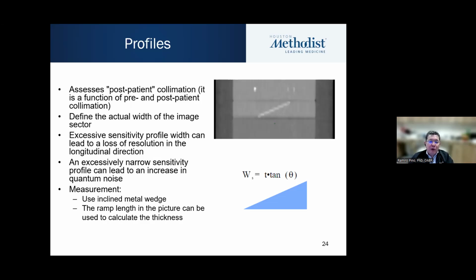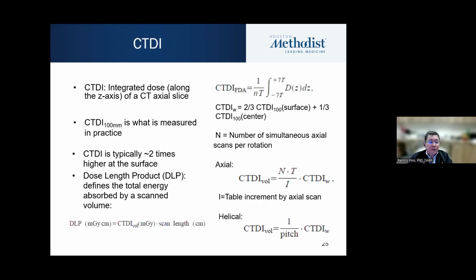And we also have the post-patient collimation, which is basically collimation before the detector array. And that will define the image itself. And again, we need to keep that sensitive profile within specs because of the implications. An excessively narrow one will lead again to quantum noise, and an excessively wide one will lead to a loss of resolution. And typically we use an inclined metal wedge for this one. For the pre-collimation profile, we typically use a film.